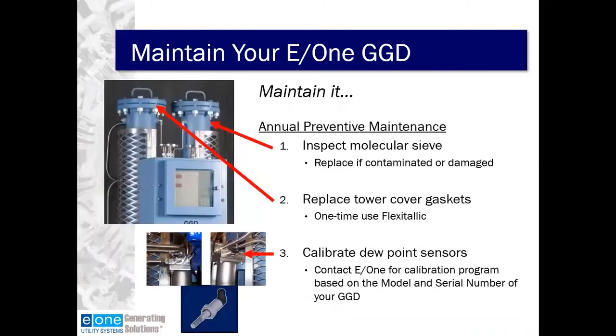From an annual preventive maintenance perspective, we have a few additional steps that we want to cover here. The first is that we want to inspect the molecular sieve. It's important that we ensure that the molecular sieve is not damaged or contaminated. In order to do so, we have to remove the top lids of each vessel. So this procedure takes place when the dryer is offline. That can be done when the generator is still running.